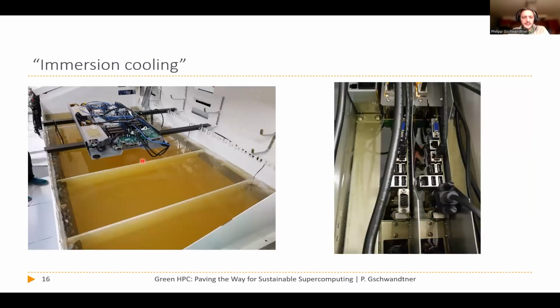The reason for that is that these are actually tanks filled with oil, and the compute nodes - one of them is just sitting on top here for illustrative purposes - are actually submerged in the oil vertically, with only the top connections outside of the oil, so you can connect the network, serial interfaces, USB if you have them, and so on. This is why it's also called immersion cooling - you really have all the hardware producing heat immersed in the cooling medium. Oil is very efficient because it's very good at transporting heat.